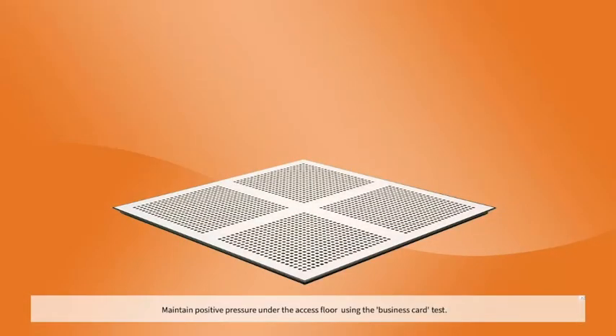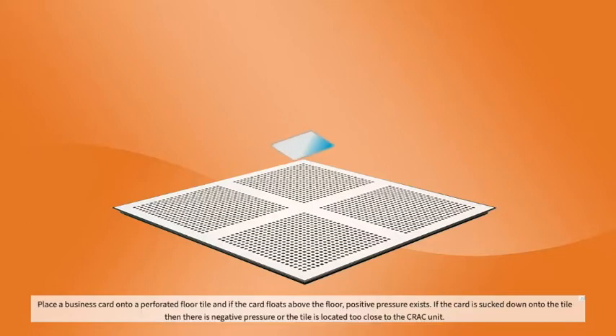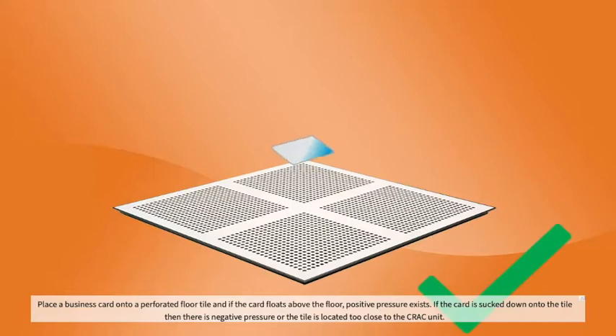Maintain positive pressure under the access floor using the business card test. Place a business card onto a perforated floor tile, and if the card floats above the floor, positive pressure exists.